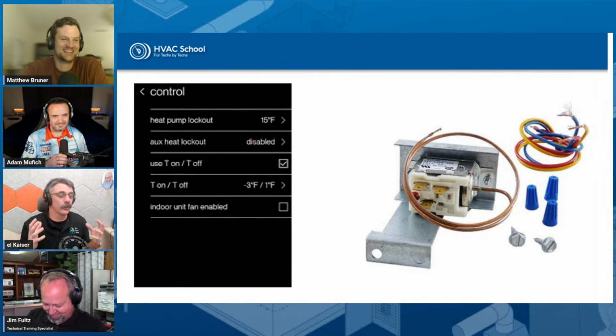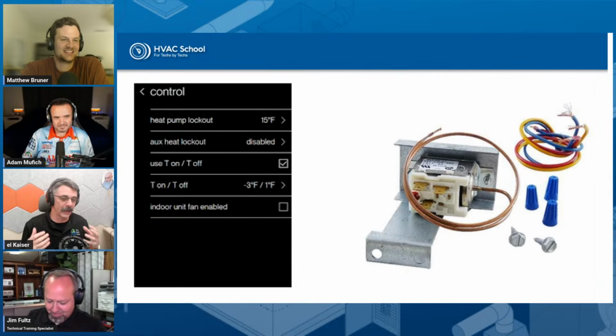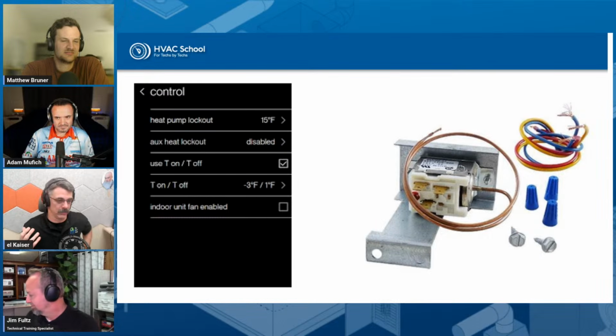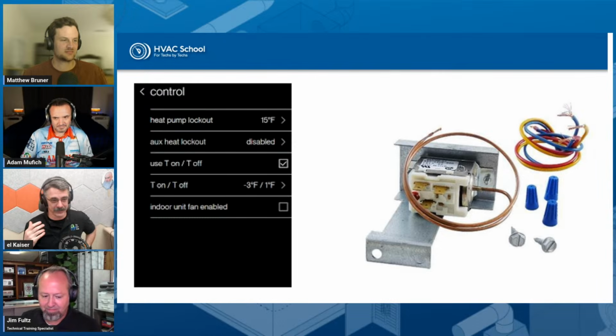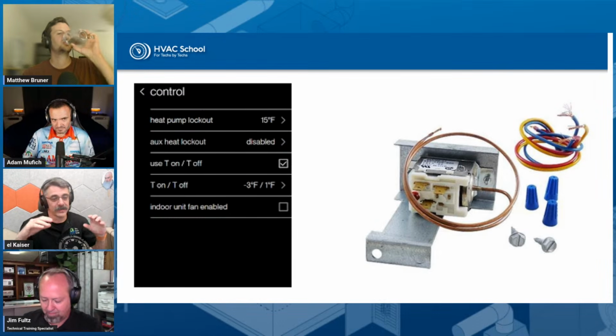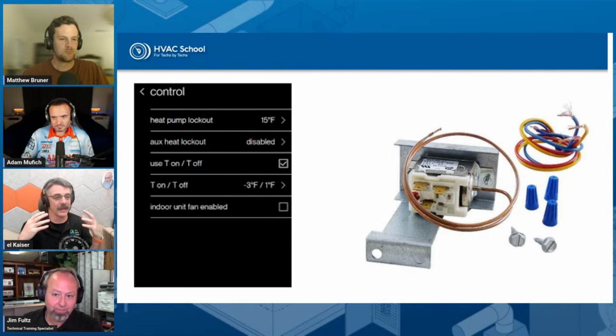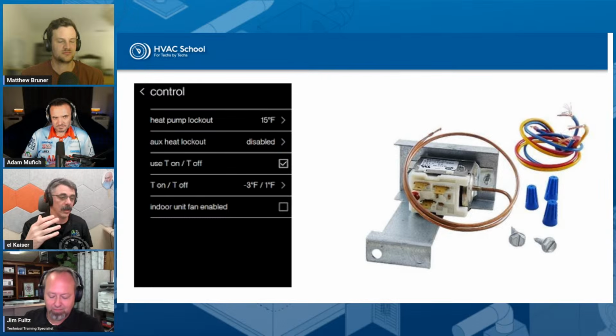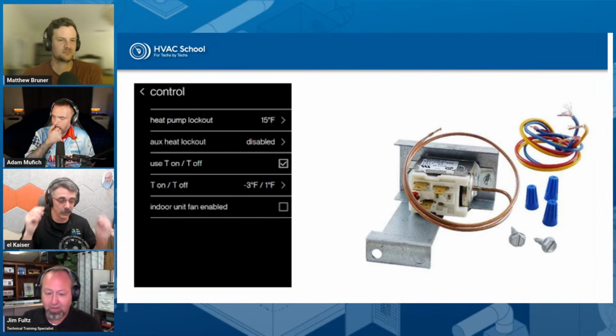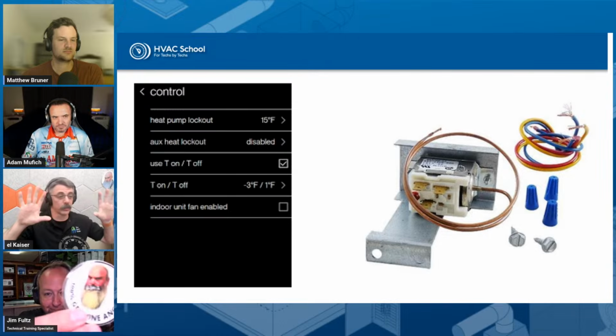I mean, literally. To me, that goes back to proper air distribution, and when I talk about air distribution in that sense, it's not ductwork. This is air distribution in the room. Where are we blowing that air in the room? We want to be blowing it on the surfaces that are taking heat out of the room. If we warm those walls up, warm the ceiling up, typically it's not the floor. Most of the time it's the walls or the ceiling losing heat out of a room. If we blow the air on those surfaces and warm them up, yeah, nice.